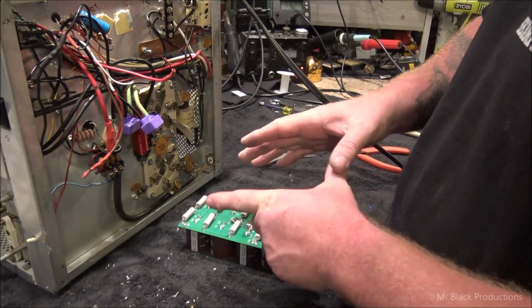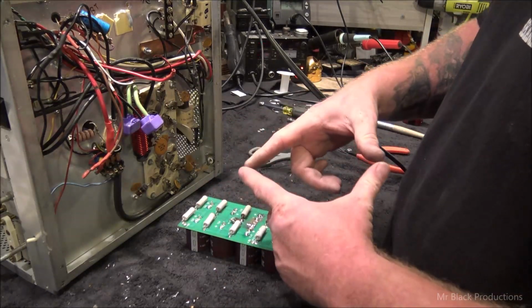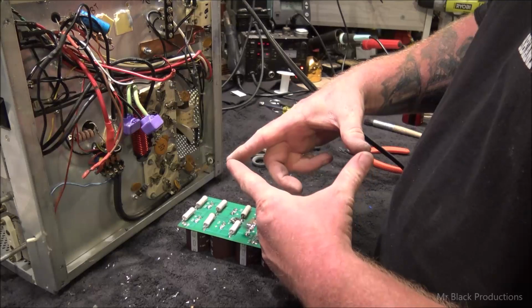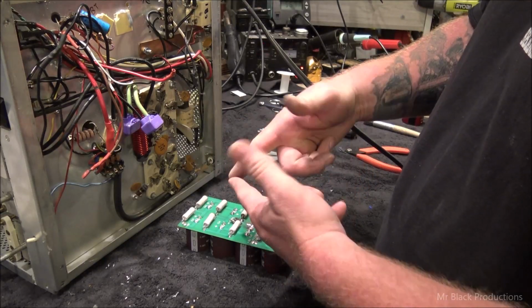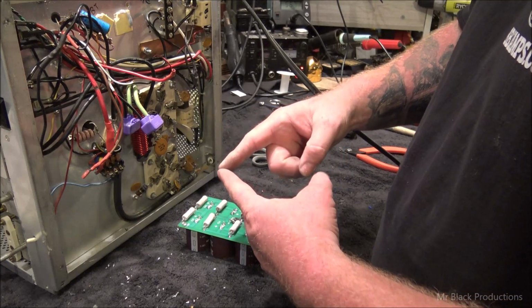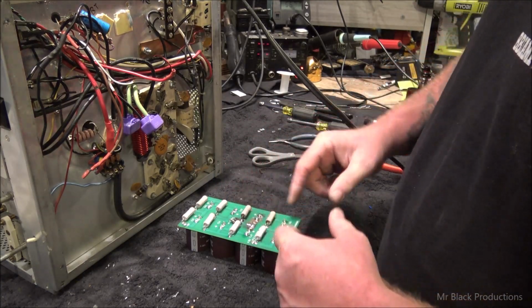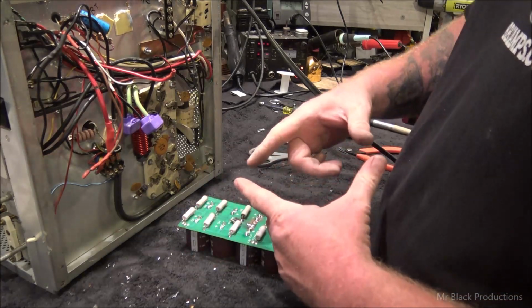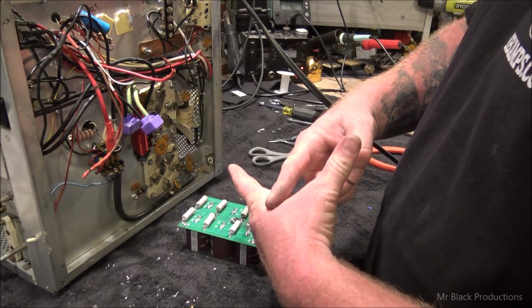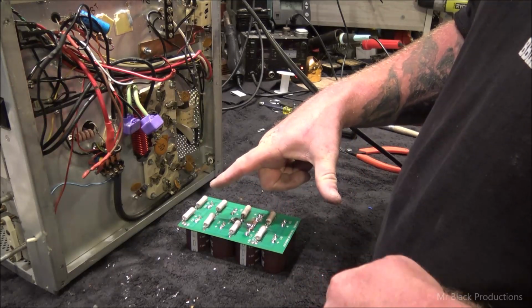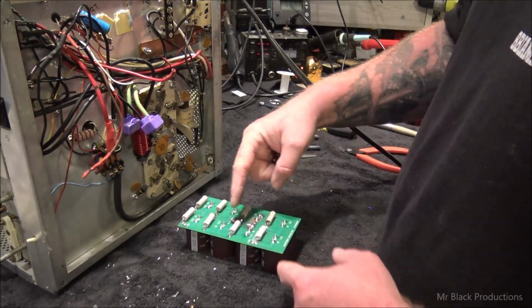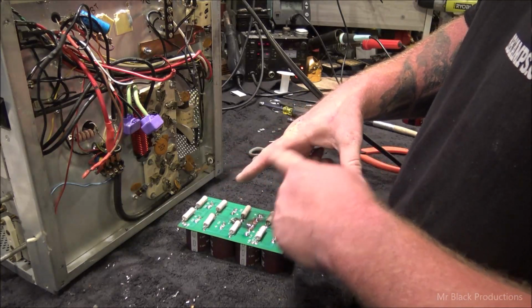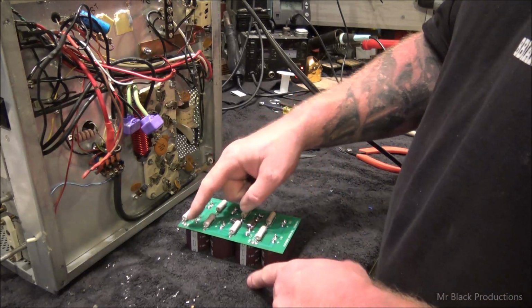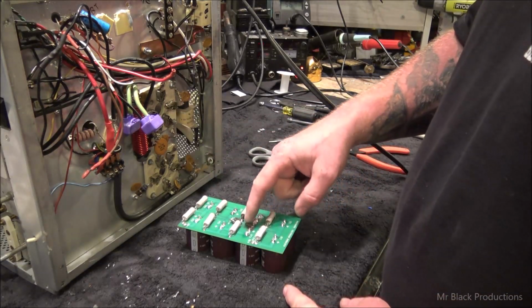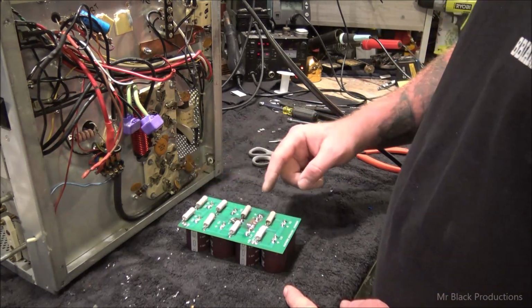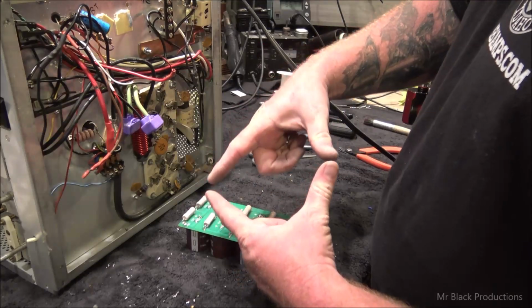So we're going to have ground, which is going to finish, you got your rectifier diamond. This is a string of diodes, this is a string of diodes. And then instead of having a string of diodes here and a string of diodes here, you're going to feed AC here and AC here into the diamond. Out one side, you're going to get positive. Usually this side, top side, positive, and then the bottom side you're going to get negative, right? Well, we replaced half that string of diodes, so we feed AC in on this string of diodes, and on this side of the diodes you're going to feed AC in, but there's no diode. Now we're using a capacitor bank, so voltage doubler works. So we got conductivity through this leg of capacitors, and we've got conductivity through this leg of capacitors, down through this set of 4 and up through that set of 4, and this is our center tap, thus completing the diamond.